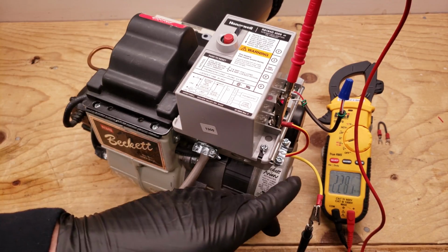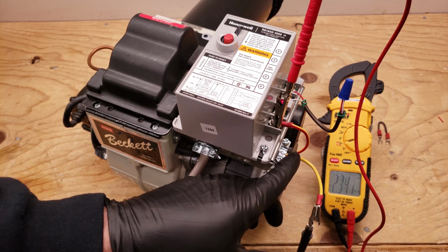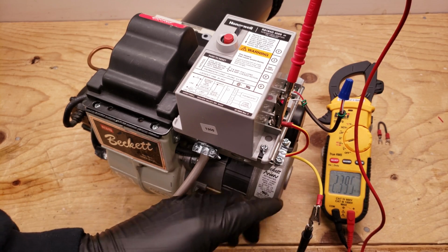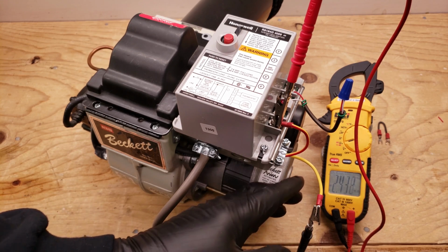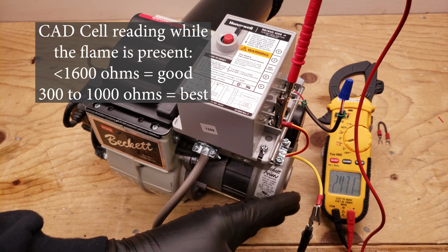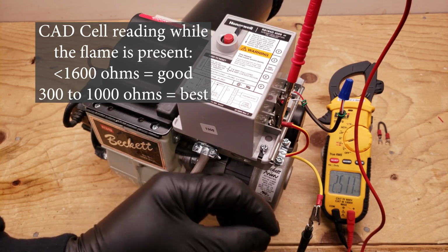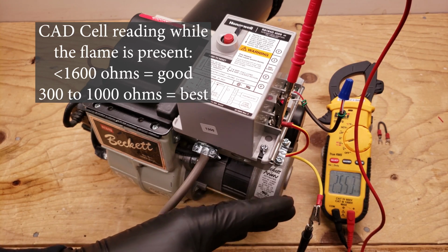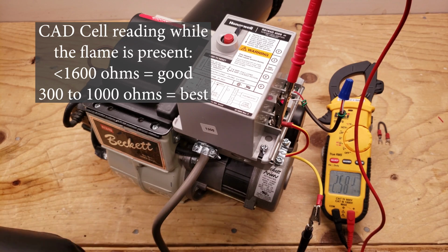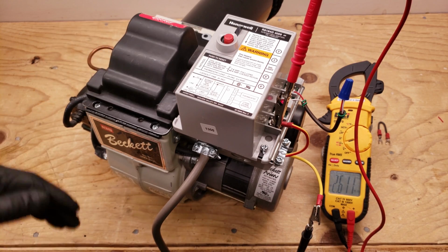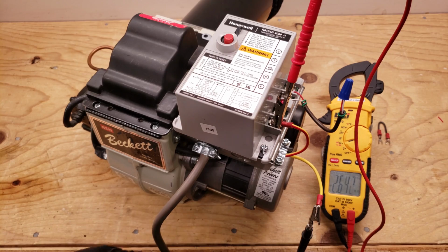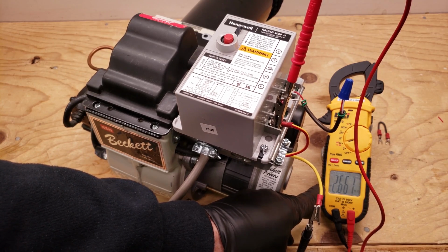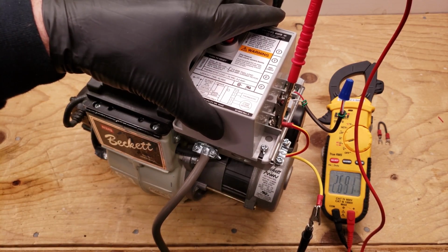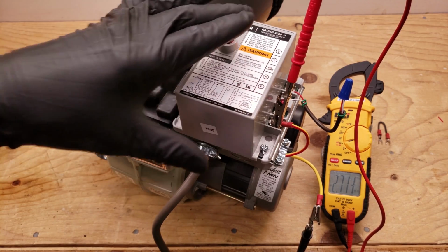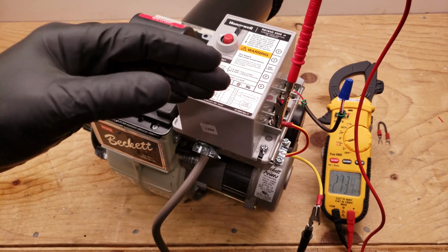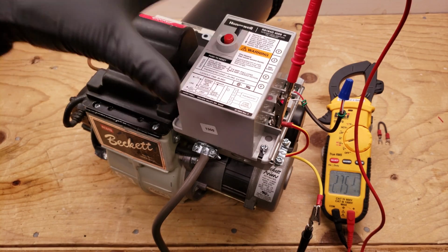But anyway, what happens is you should have a resistance value on the CAD cell even lower than 1100 ohms. You should be down between, say, 300 and 1000 ohms, and that would indicate that you have a good flame. If it's higher than that, you may not have a good flame, or maybe the CAD cell is dirty or something like that. But you want to have anywhere below 1600 ohms in order for this primary control to sense that you have a good flame. Once again, if you have something between 300 and 1000 ohms, that's better for the flame.